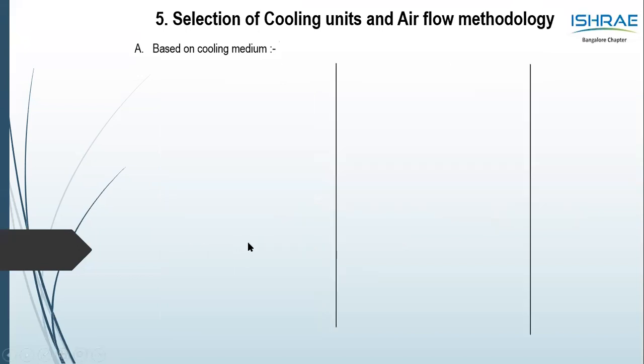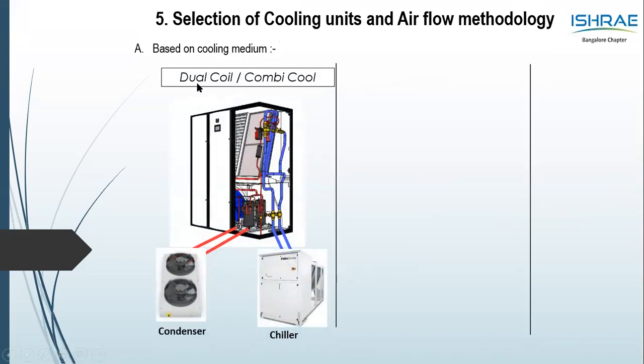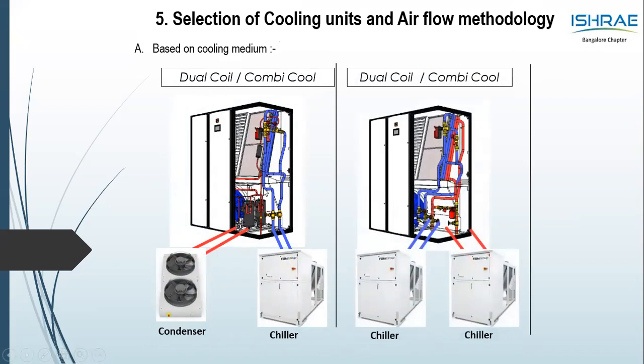So based on the cooling medium, then we look at the dual or the combi cool, where the same CCU units are connected to DX with the condenser or the chiller. The concept is in any server room data center, morning 9 to 5, 9 to 6, when the chiller is on, it goes into the chiller mode. Evening, when the ambients are low, when the chiller is shut down, it goes into the DX mode. And then you also have the benefit of the combination of chiller plus chiller can be working standby or 7/12 or 15/20, but all these options, either one of the above can operate at a given time.